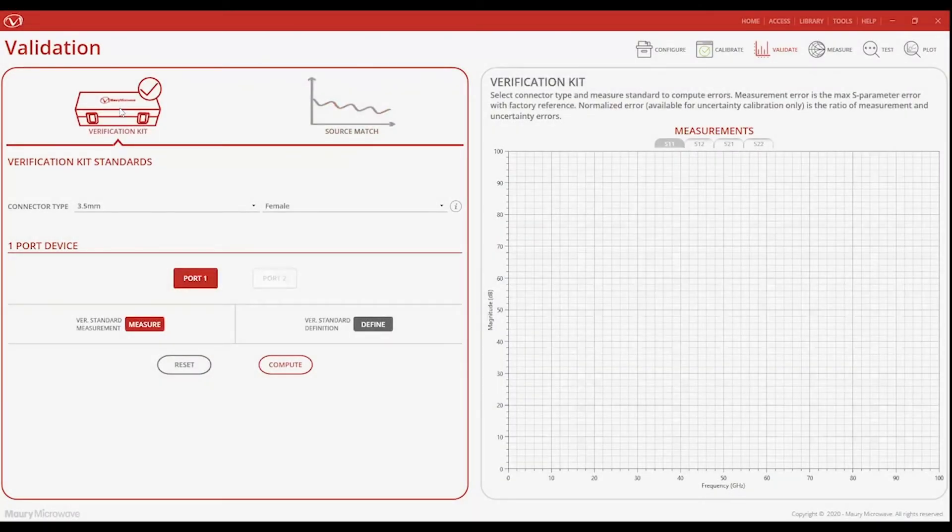Maury verification kits come with characterized verification standards that are meant to mimic your specific device under test. What comes in the kit are precision loads that are used as embodiments of a well-matched one-port device, and for those poorly matched one-port devices, you can use the offset shorts included. And for those of you who are calibrating two-port, there is a precision airline as an embodiment of a well-matched two-port device, and a mismatched airline for the poorly matched two-port devices.